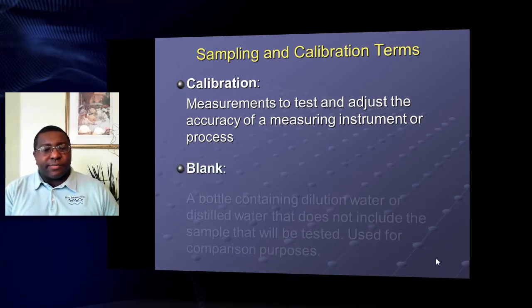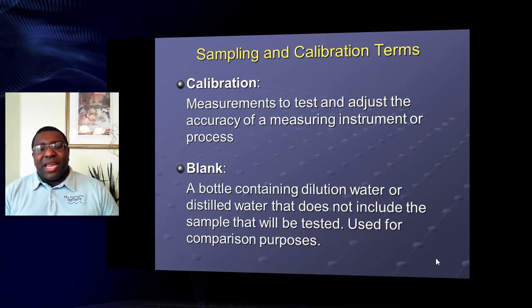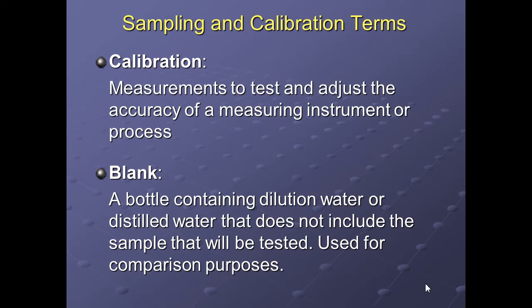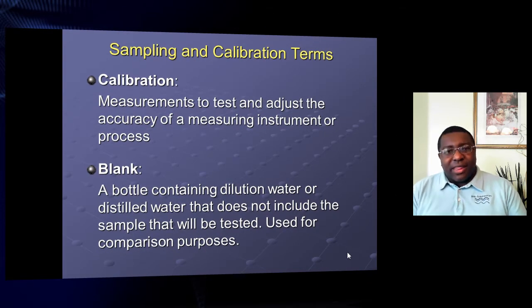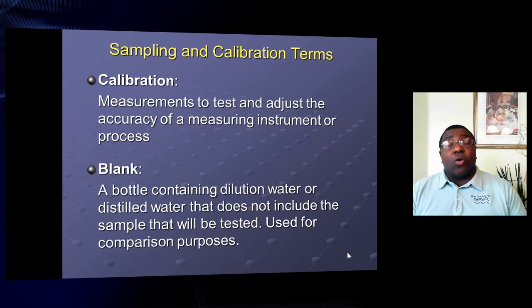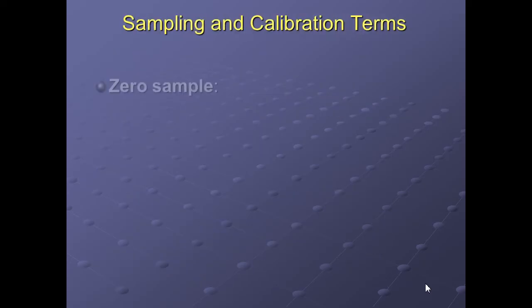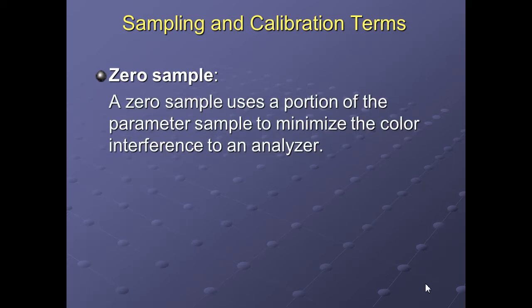A blank is a bottle containing dilution water or distilled water that does not include the sample to be tested — it's for comparison purposes. Most meters need one reference sample cell versus the sample cell that has the sample and reagent. The machine gives you a reference from one cell to the next so you know there's a reaction, and that amount of reaction tells you what that sample concentration is.